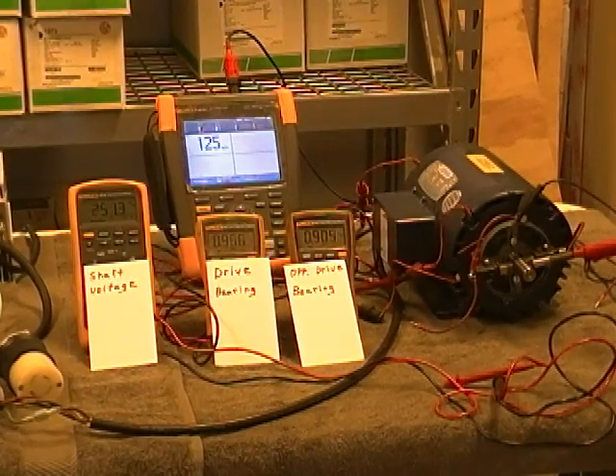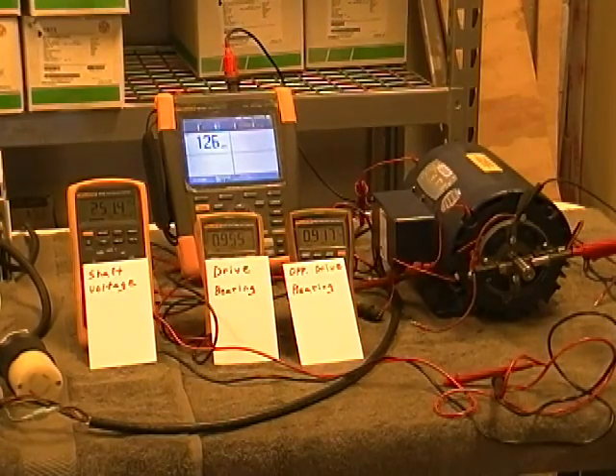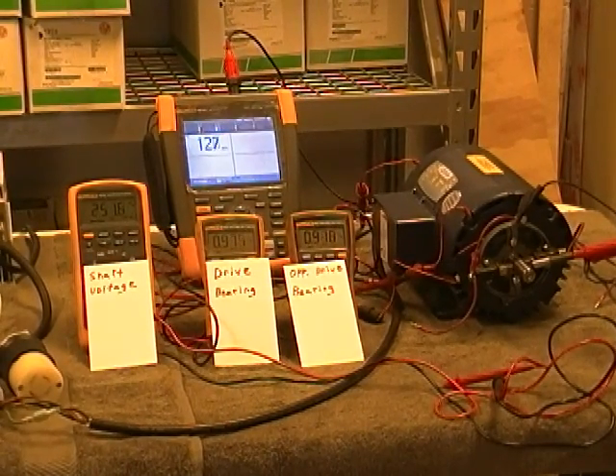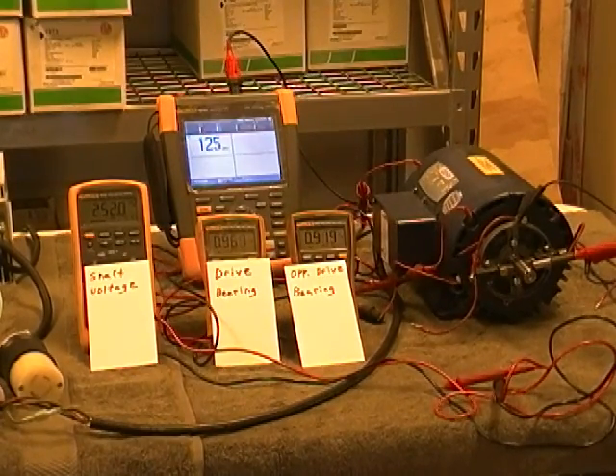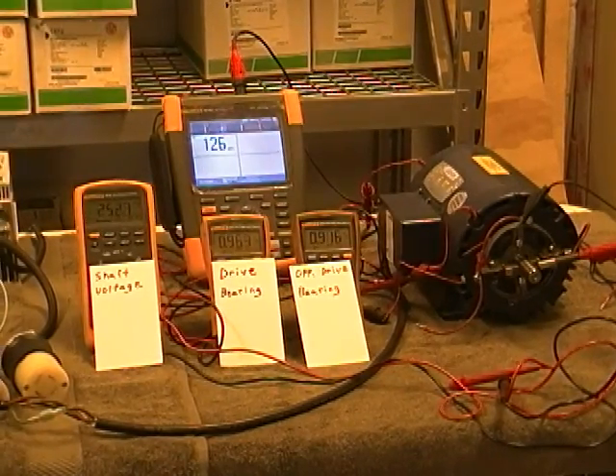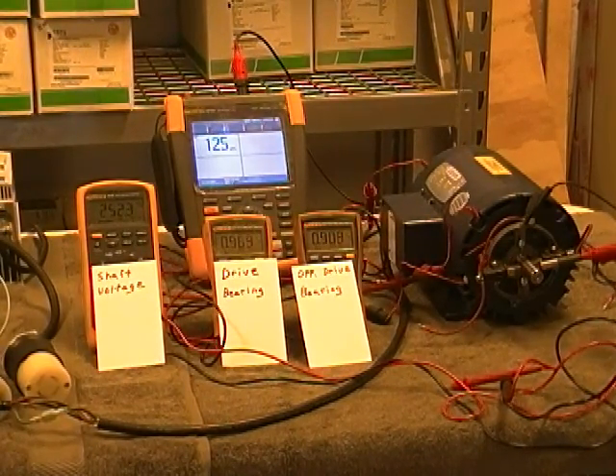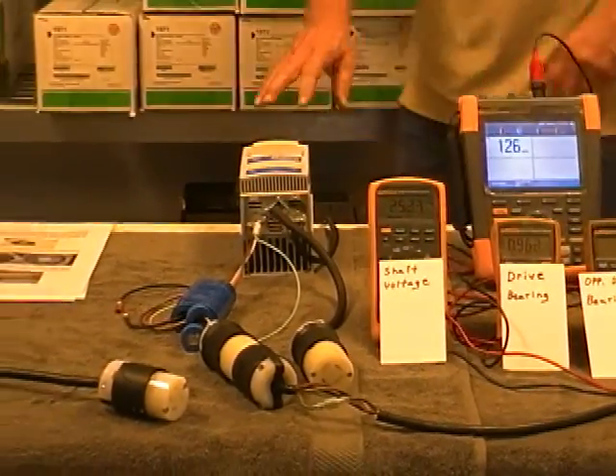Remember, Cool Blue is only used for high frequency current, for bearing parasitics, to help clean up the high frequency current on the ground wire. We have found little to no effect on voltage. But that shows us that voltage is not the issue — it's based on current. Our next test will prove this.